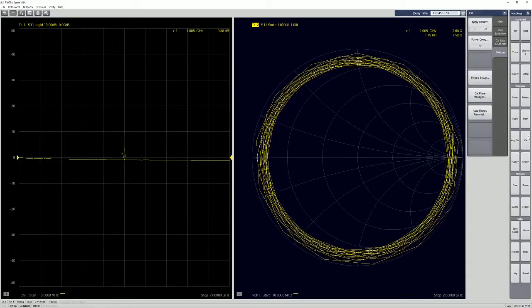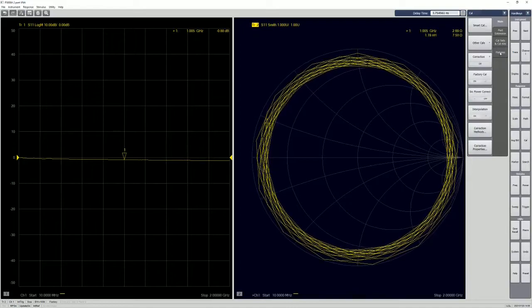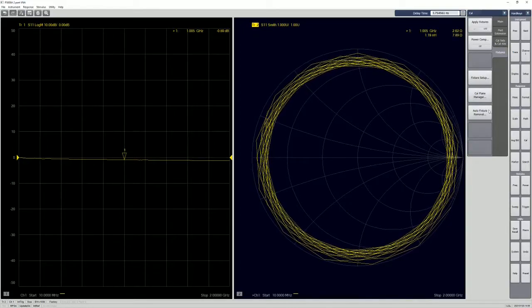So just go to cal, fixtures, auto fixture removal. So because this is open-ended, single-ended, and only use one port, so it should be something like this. And just click and just leave the rest as it is right now. I can create another video just to cover the rest of the setup.